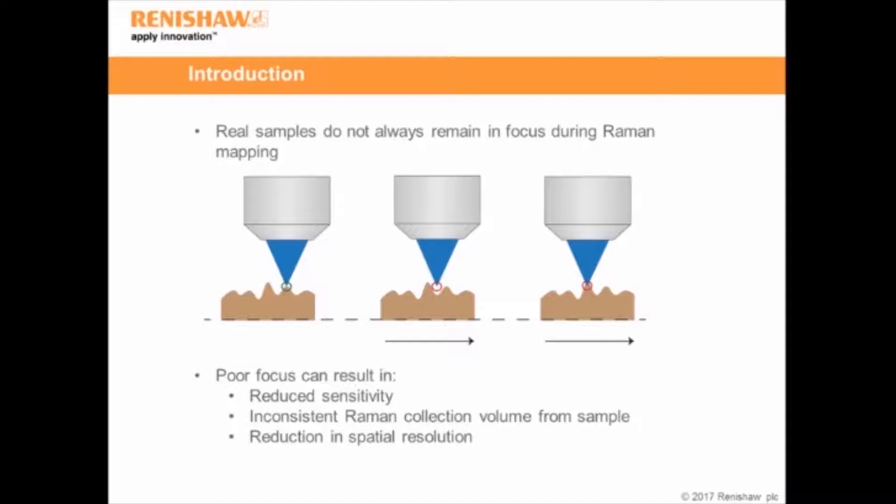This poor focus can result in reduced sensitivity, so we lose Raman intensity. It also changes the actual Raman collection volume from the sample, so we can no longer use intensity-based methods to make measurements in a quantitative form. It also reduces our spatial resolution.